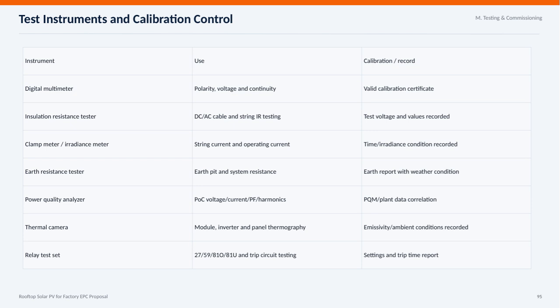The insulation resistance tester measures the resistance of DC and AC cables and strings, with test voltages and values carefully recorded. We also use clamp meters and irradiance meters to monitor string and operating currents, making sure to log time and irradiance conditions for accurate assessment. Earth resistance testers are employed to verify earth pit and system resistance, accompanied by earth reports that include weather conditions. The power quality analyzer plays a vital role by measuring point of connection voltage, current, power factor, and harmonics, correlating this data with the plant's performance.